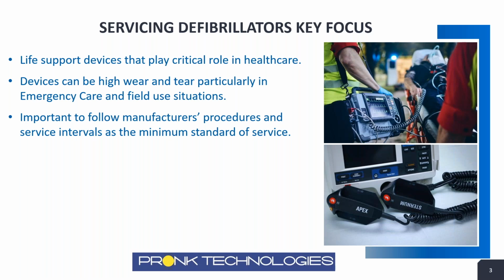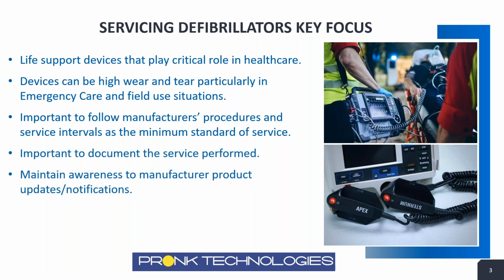Defibrillators do have some unique testing requirements depending on the brand, so it's important to understand some of the differences from brand A to brand B. They're not always the same type of testing you have to do on these devices. And then it's important, of course, that we document this information. These devices come under a lot of scrutiny, so it's important we have our documentation very clear as to what we tested, what the pass-fail results were, and such, so that we're clear that we've documented everything properly.